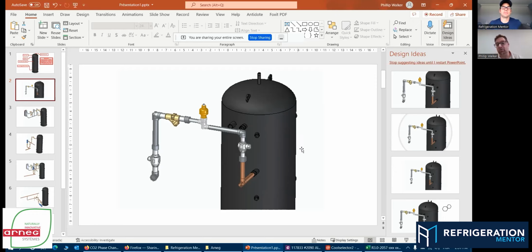So it gives a better control over the flash tank throughout very cold winter days, because some of the areas that we deliver these machines, we honestly see guys like minus 25 to minus 30 degrees Fahrenheit at certain periods of the year. And so that would be really good for control guys to understand, because at first you would think, oh, this is really difficult. You get 2 flash tanks, you get 2 valves, but it will be all in the programming, where I'm assuming that it hits a certain temperature and then it'll switch the whole system over, and it's done automatically. It's not like something you have to go in and continue to adjust. I assume this will be all built into programming, so it happens on its own.